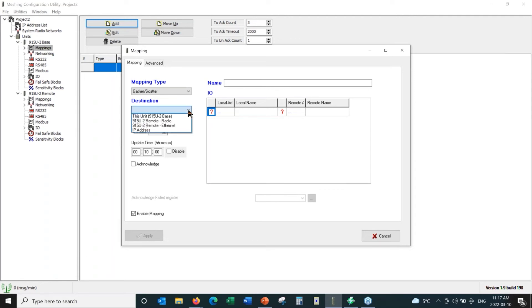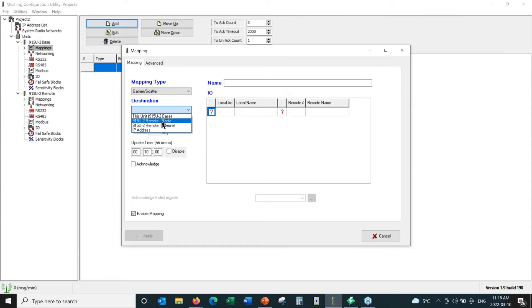I'm going to set up a gather scatter mapping. I have to select the destination — where do I want to send this data? I'm connected to the base radio and I want to send it to the remote radio. You can send commands out the radio port, which we do about 99% of the time, or we can send to the Ethernet port. Since these radios are connected via radio link, we almost always select the remote radio's radio port.